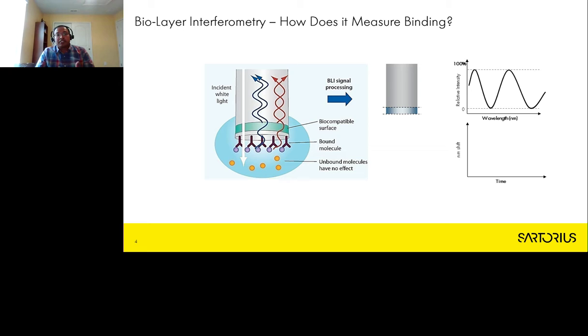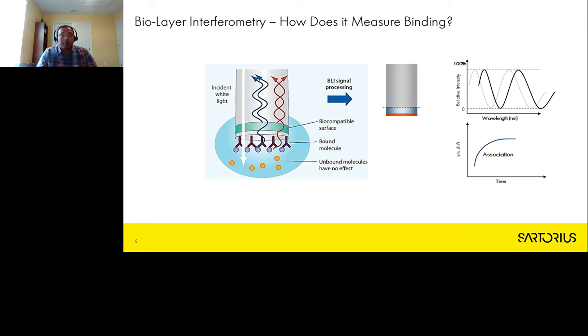As the biolayer thickness increases, the detector sees light wavelengths traveling slightly longer distances, creating an interference pattern. This enables real-time calculation of association rates as the signal increases when the binding complex forms. During dissociation, the thickness of the biolayer decreases, providing a kinetic measure that gives the dissociation rate constant and affinities.